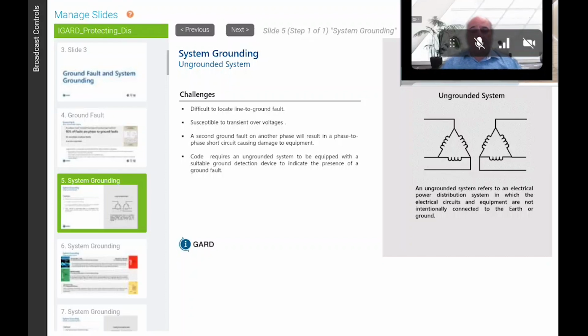If a second fault occurs, if you have a ground fault on an ungrounded system, you've basically converted it to a solidly grounded system. So the next fault is going to be a phase-to-ground fault as if it were a solidly grounded system. So you don't have ground fault protection according to the NEC and CEC. What there is, is ground fault detection. So you have to annunciate the presence of a ground fault in an ungrounded system.